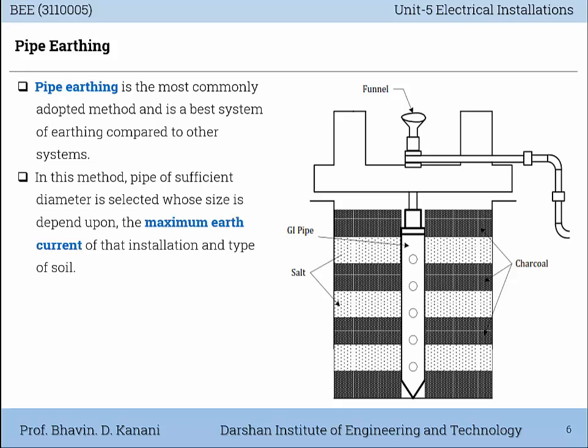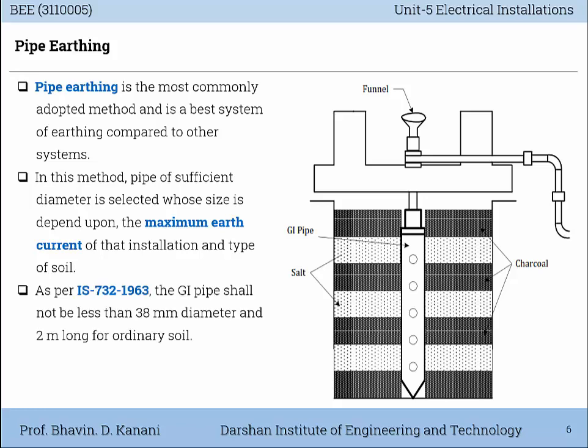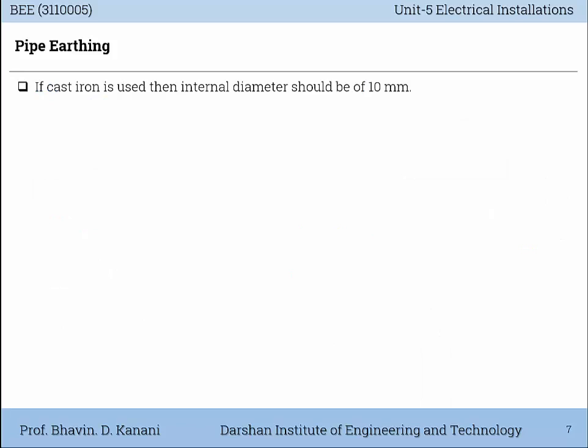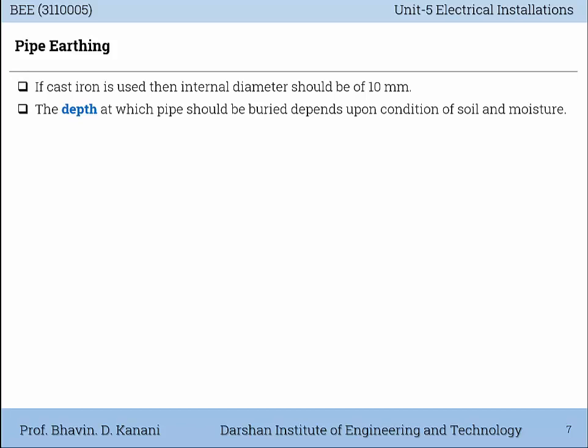In this method, a pipe of sufficient diameter is selected, whose size depends upon the maximum earth current of that installation and the type of soil. As per Indian Standard 732/1963, the GI pipe shall not be less than 38 mm diameter and 2 meters long for ordinary soil. If cast iron is used, then the internal diameter should be 10 mm. The depth at which the pipe should be buried depends upon the condition of the soil and moisture.